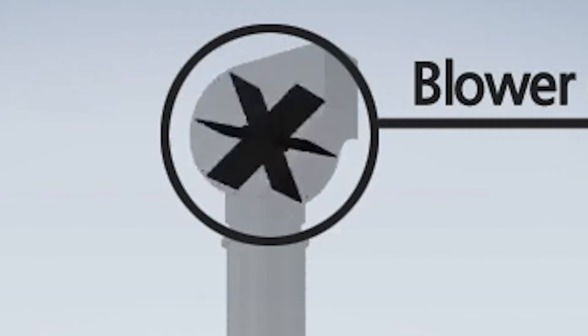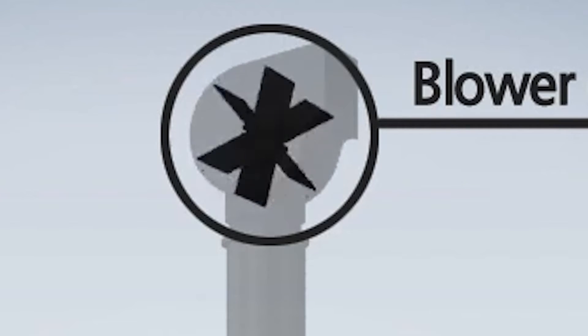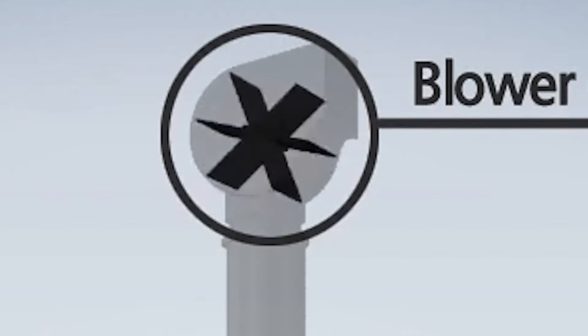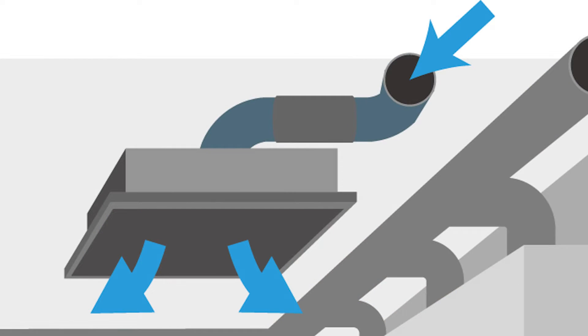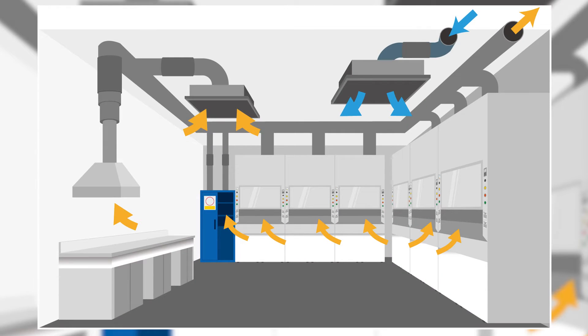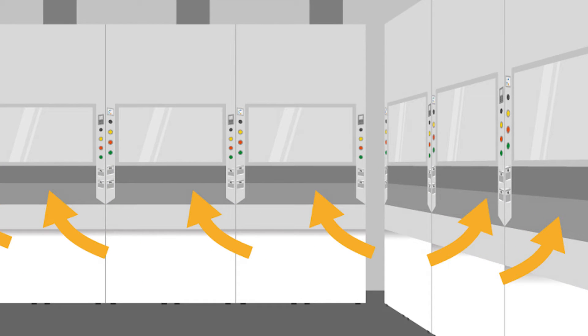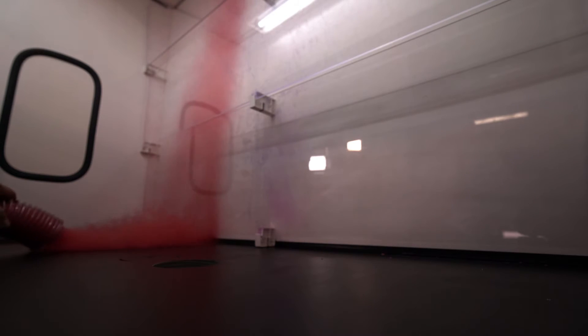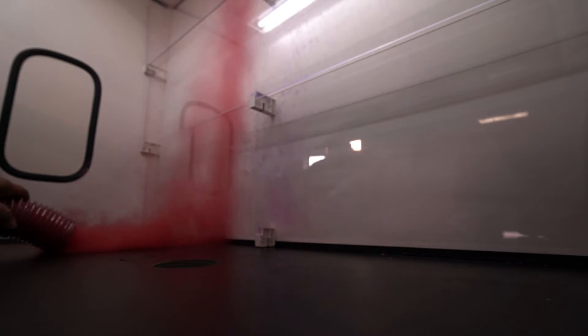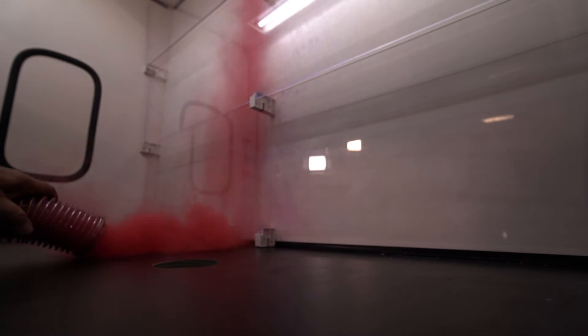You could say that the fan is sucking the air through the hood. Airflow is designed to flow from clean to dirty areas — the clean air from the corridor flows into the lab, the lab air flows into the hood through the sash opening, then into the plenum, then the ductwork to the exhaust fan, where it's usually exhausted out of the building.